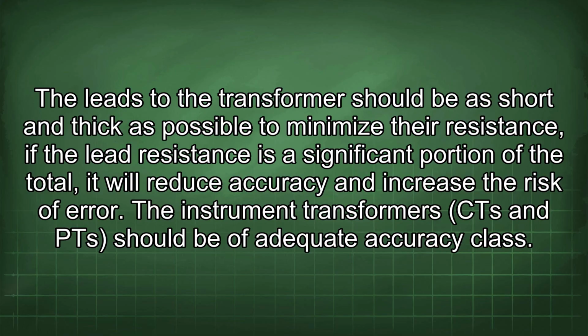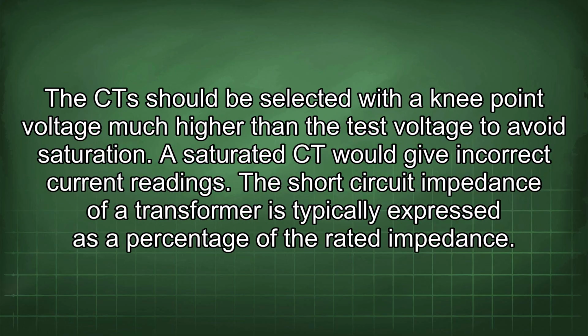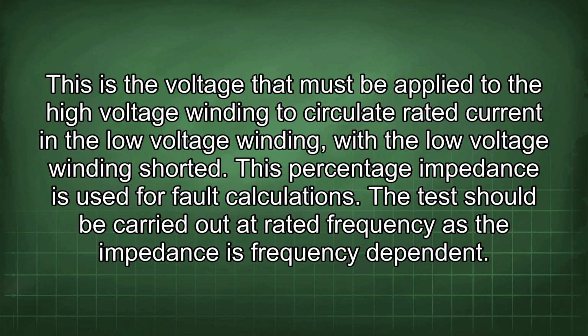error. The instrument transformers CT and PT should be of adequate accuracy class. The CT should be selected with the knee point voltage much higher than the test voltage to avoid saturation. A saturated CT would give incorrect current readings. The short-circuit impedance of a transformer is typically expressed as a percentage of the rated impedance. This is the voltage that must be applied to the high-voltage winding to circulate rated current in a low-voltage winding, with the low-voltage winding shorted.